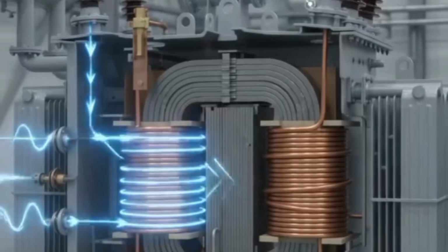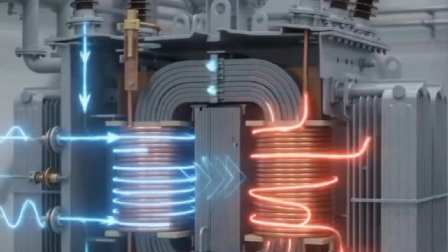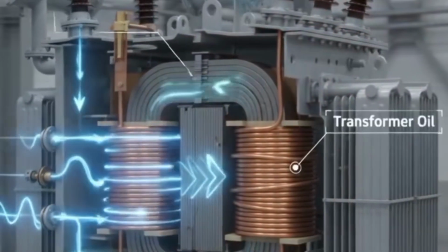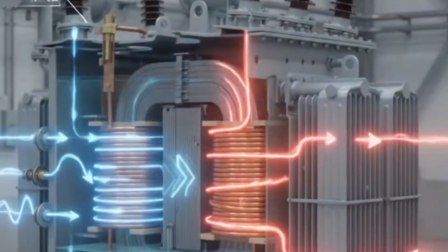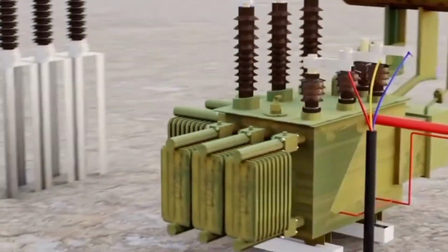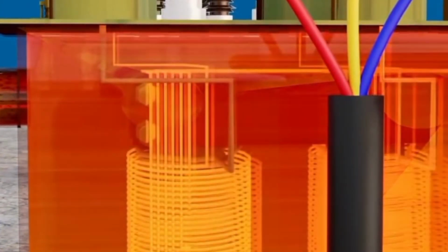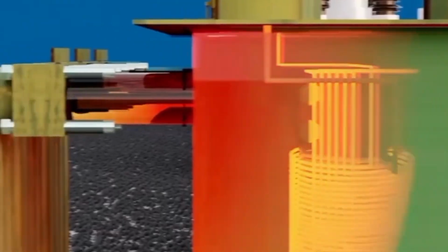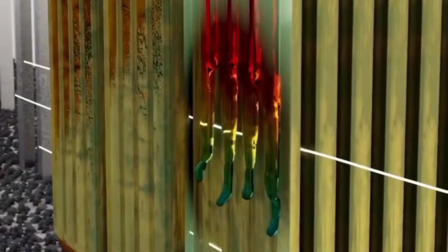and minimal heat generation. Wrapped securely around this laminated core are two distinct sets of electrical coils, commonly referred to as the windings. Made of highly conductive copper or aluminum, these coils are divided into the primary winding and the secondary winding. The primary winding is the input side, which receives the incoming alternating current electricity from the power source. The secondary winding is the output side, which delivers the modified voltage to the destination. It is important to realize that there is absolutely no physical or direct electrical connection between the primary and secondary copper coils. They are completely insulated from each other.